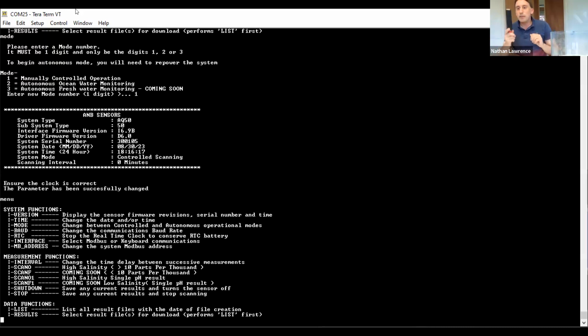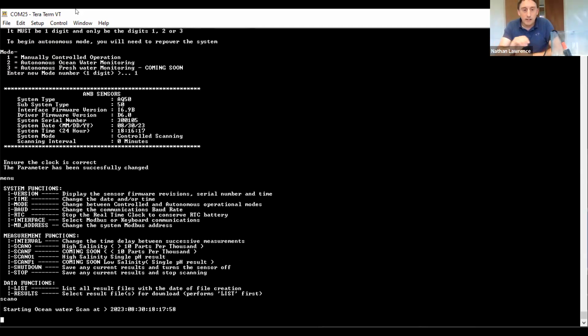For now, we're going to put the sensor into a seawater solution. There is solution in this beaker, even though you can't see it. And we're going to do a scan-O function. So it gives you feedback that the sensor is now scanning. While it's taking its first measurement, I'm going to stop the share and talk to you about how we can replace the transducer and how we can maintain the transducer.